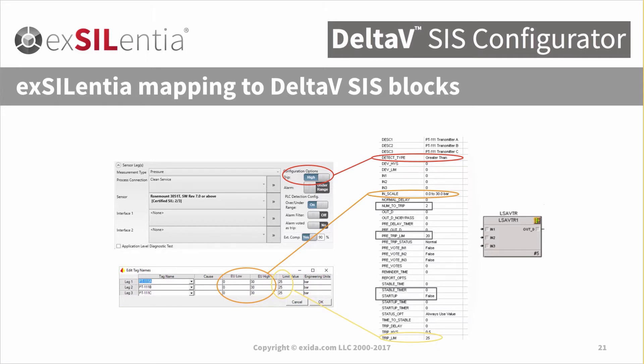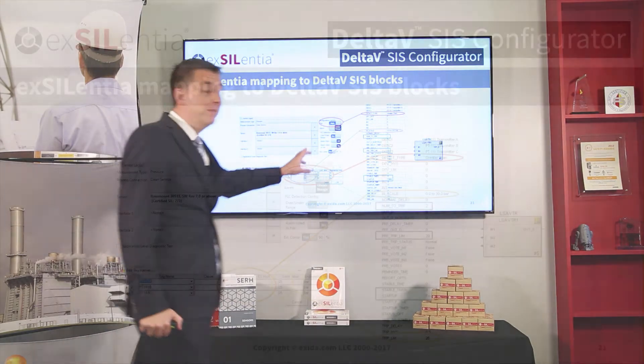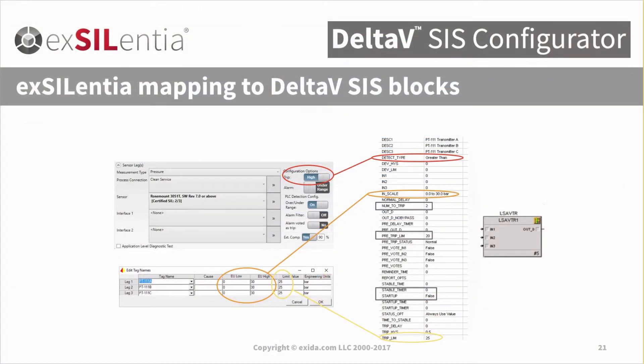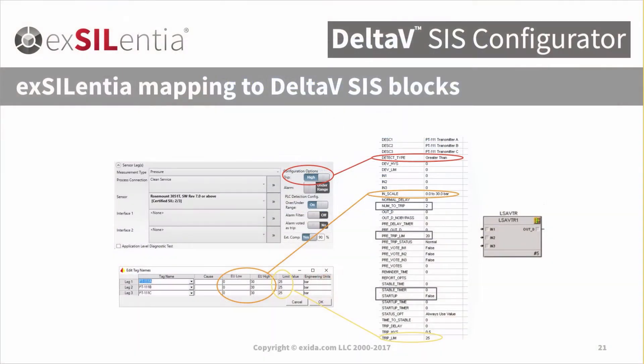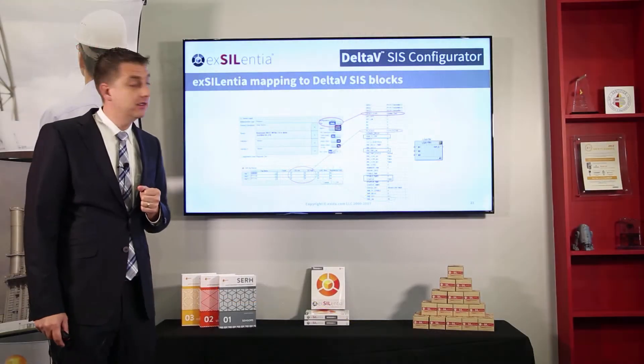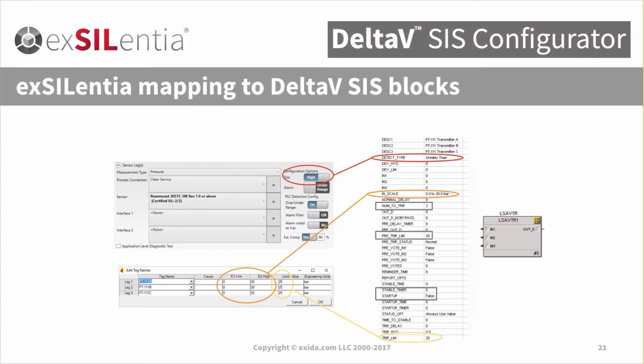Let's look at some configuration options for the sensors. We have a high trip or low trip selection, indicating if your trip point is above or below your typical process value. Based on that, we specify that we're going to trip if the process value is greater than the trip limit — defined in exSILentia. The range 0 to 30 bar defined in exSILentia shows up directly here. For a two-out-of-three voter, the number to trip is two.